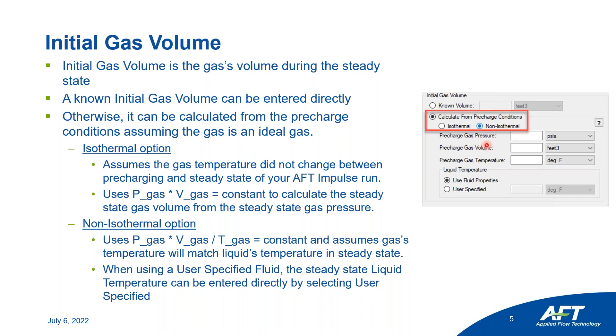We have pre-charge gas pressure, pre-charge gas volume, and pre-charge gas temperature to enter as inputs. You have to enter all three if you're doing the non-isothermal option, which assumes ideal gas and uses the equation P times V over T equals constant. If you don't know the pre-charge temperature, you can assume isothermal to get an estimate and just use the pressure and volume of the gas at pre-charge.